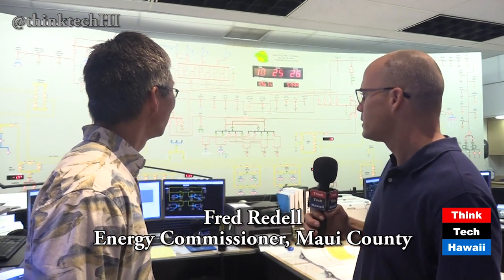On the control room board, the Kaheawa Wind Farm shows a digital readout of minus 16.8, meaning it's feeding about 16 to 17 megawatts into the system. The center has SCADA control and visibility over all three islands: Maui, Molokai, and Lanai. When wind is up and sun is shining, operators regulate diesel generators down to accept as much renewable energy as possible. The possibility of microgrids is acknowledged, but the key question remains whether they can provide reliable, cost-effective service to customers.